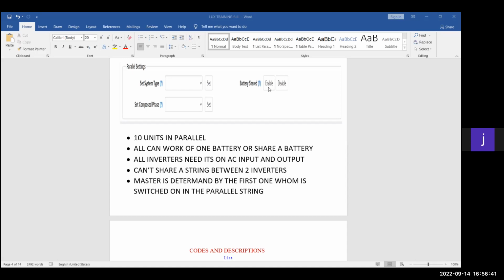So battery shared just gives you the capability to keep all your inverters on the same battery bank, especially in a three-phase system. In a three-phase system, your phases aren't balanced 100%. So if you have a 5 kilowatt battery on all three phases, one of your phases will drain its battery faster than the rest of the phases, and your inverter will switch off at a certain point if your battery is flat. And as soon as you lose a phase in a three-phase system, the system will completely shut down, and your whole system will be dead until your battery power is sufficient for the system to start up again. Now you still have 3 kilowatt in the one battery left, and the other one has a kilowatt left. So you have technically 3 kilowatts worth of power that you can still use. But one of my phases' batteries is dead.